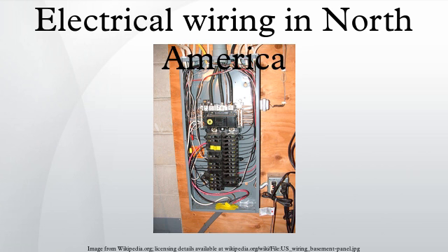An older, but still widely used high-leg delta system uses three phases with 240 volts phase-to-phase for motor loads, and 120 volts for lighting loads by use of a center tap transformer. Two of the phases are 120 volts to neutral. The third phase, the "high leg" of the system, has 208 V to neutral and is not usually used for single-phase connections, so is distinctively colored. For larger commercial installations, 277/480 V or 347/600 V three-phase is common.